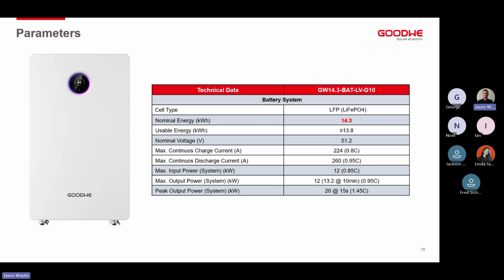Quick look into some of the technical data on the battery system. So usable energy is 14.3 kilowatt hours. Nominal energy is 14.3 kilowatt hours. Usable just under 14 kilowatt hours. The nominal voltage is 51.2 volts. Maximum continuous discharge is just under 1 C. And maximum continuous charge is 0.8 C.